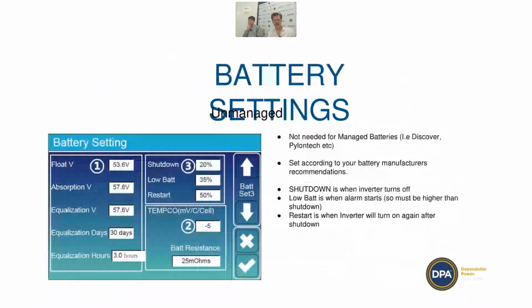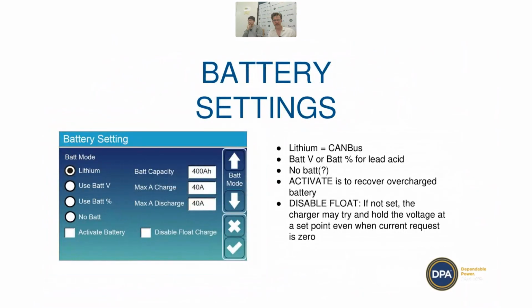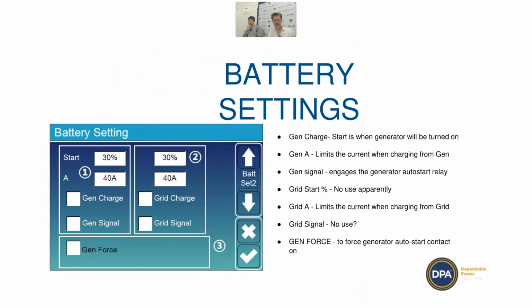So when you're commissioning that, I suggest that you set it. Here we are. So it's in this setting here. You want to have generator charge ticked, and you want to have gen signal ticked. And that means that the dry contact will turn on when it gets below 30%, and it will charge at this rate. You can test it by clicking this button here, Gen Force, and then obviously you have to click the tick down the bottom here.